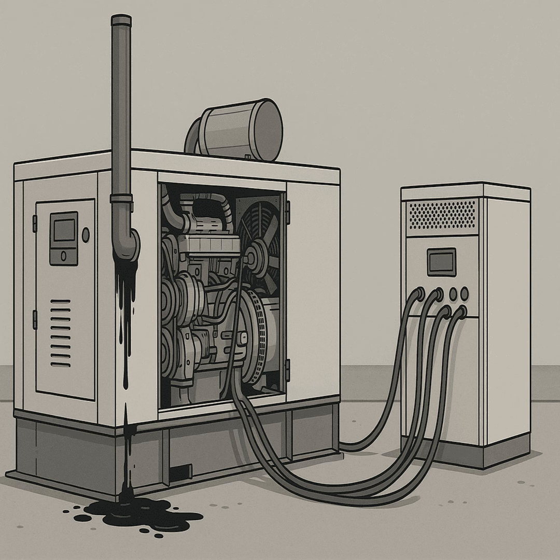The gold standard, the most widely recommended solution, is load banking. Load banking. Explain that for us. Sure. Load banking involves connecting the generator to an artificial electrical load, basically, a device that simulates real-world electrical demand. The whole point is to deliberately force the generator to work harder, to run under a significant load. This raises the engine's internal temperatures and pressures up to their optimal operating range. And that heat does what? It burns off the accumulated gunk. That higher temperature allows the engine to properly combust any unburned fuel residues and carbon deposits that have built up in the cylinders and exhaust system. It's like giving the generator a really good internal cleaning through hard work. A workout, like you said earlier.